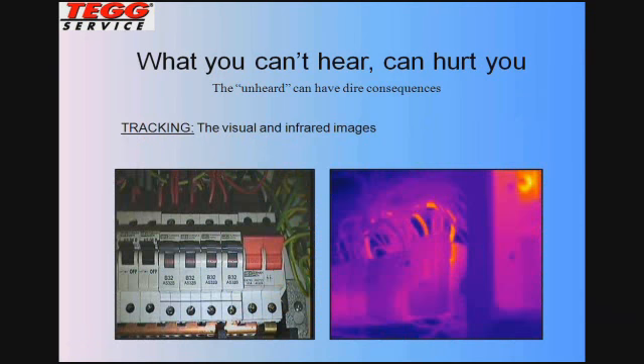And you can see that here on this slide. I have both the visual image and the digital image of that particular device. And it's only a 60 amp circuit breaker. But on the sound file, it was very clear that we had the traditional buzzing sound with the snap, crackle, pop. And when analyzed, we could see that pattern, particularly in the time domain, that had the broadband white noise, the asymmetrical excursions, and the varying amplitudes and spacing throughout the recording.